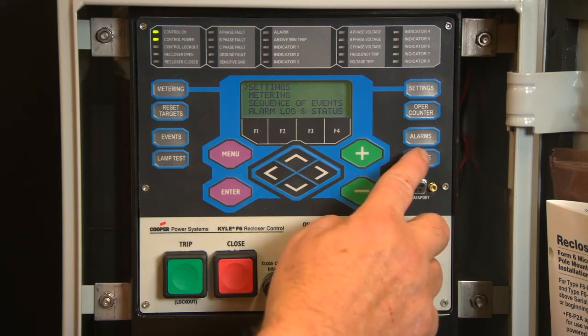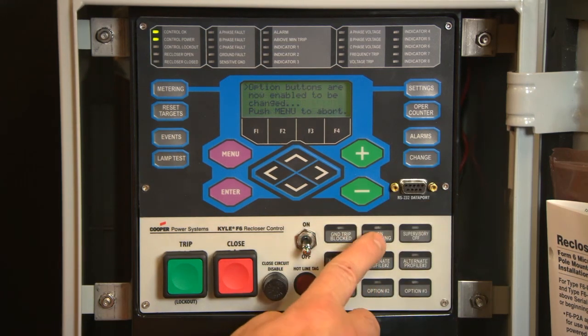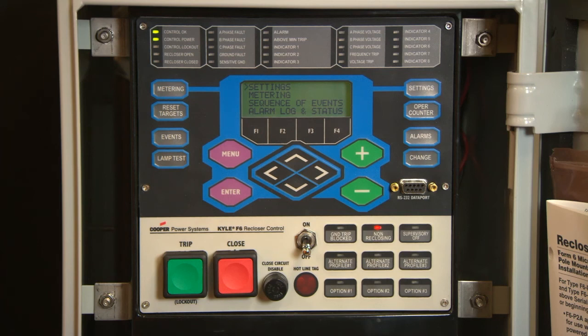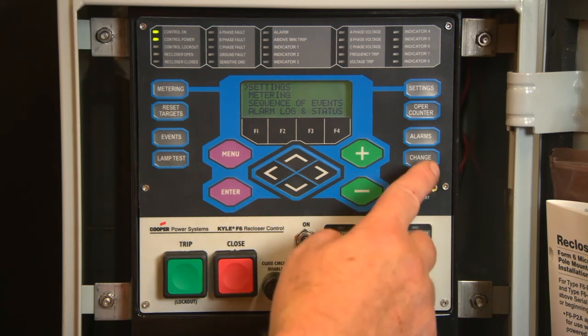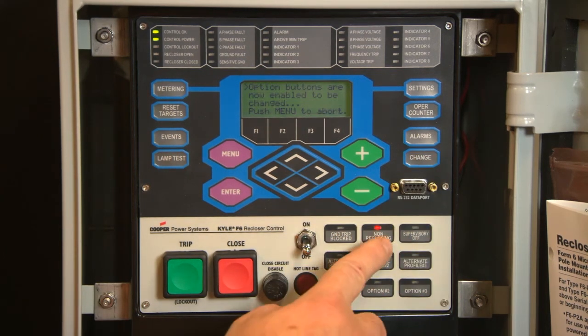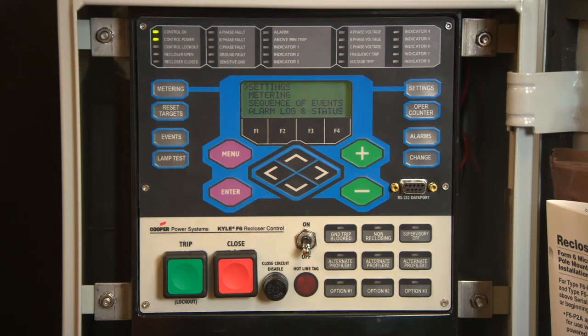Non-reclosing. Press the Change button, followed by the Non-reclosing button. This will give you one shot until lockout. This is not a hotline tag. Pressing the Close button can still close the control. This is strictly for testing purposes. Press the Change and Non-reclosing button again to turn this feature off.